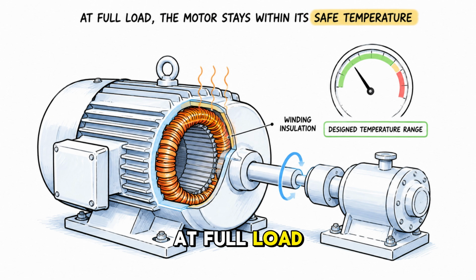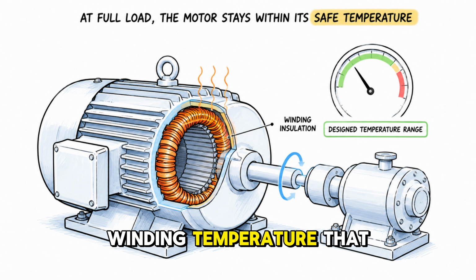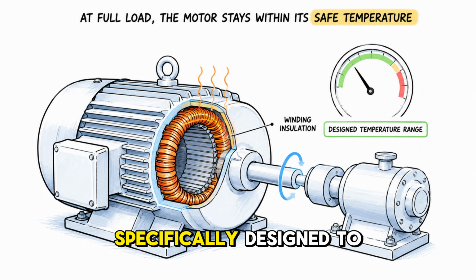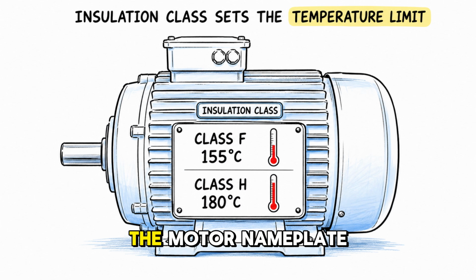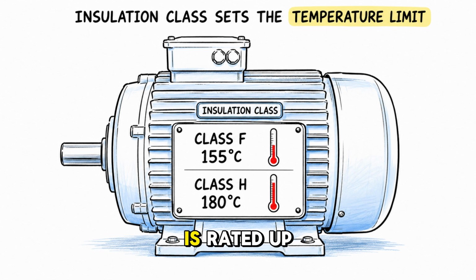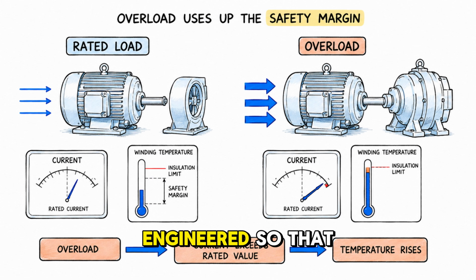At full load, a standard motor runs at a winding temperature that its insulation is specifically designed to handle. The motor nameplate shows this as an insulation class. Class F insulation is rated up to 155 degrees Celsius. Class H is rated up to 180 degrees Celsius. The motor is engineered so that, at its rated load, the winding temperature stays safely below the insulation limit with a built-in safety margin. But at an overload, the current exceeds that rated value.